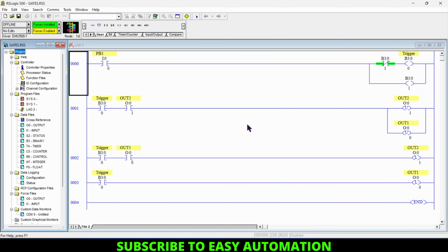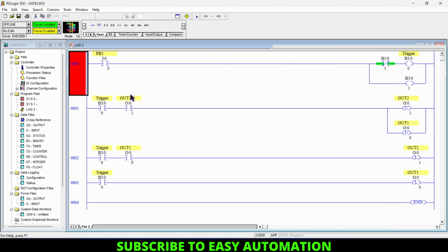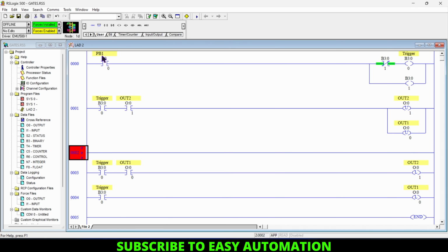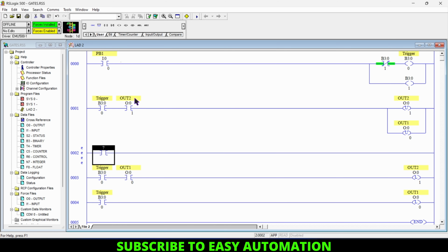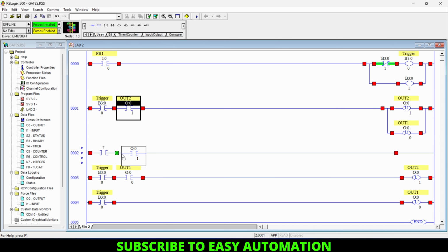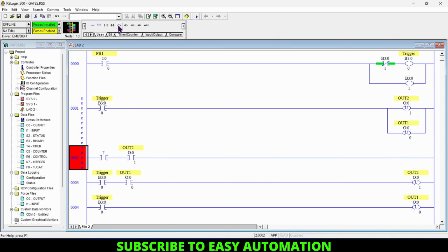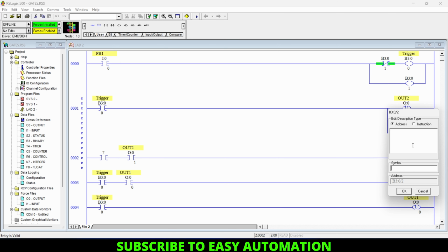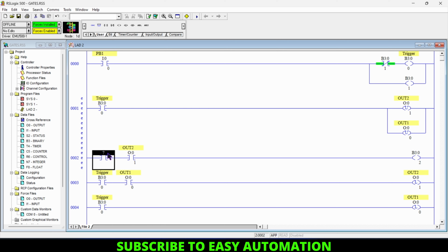So now we need to create one difference here. For that we need to add one rung here, and add one NO contact here, and drag this NO contact to this difference rung, and add one output coil here, and address this with one memory bit. For this NO contact we need to give the trigger pulse address. And now we need to give this address to our NO contact, because this address will create the difference. So now let's download.